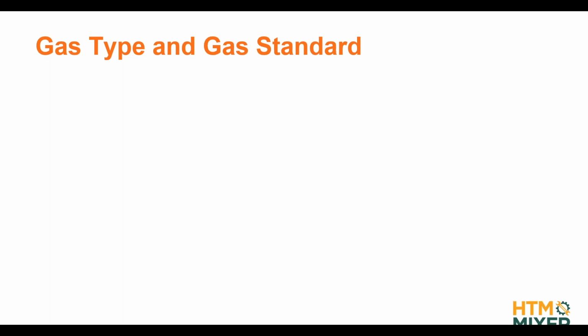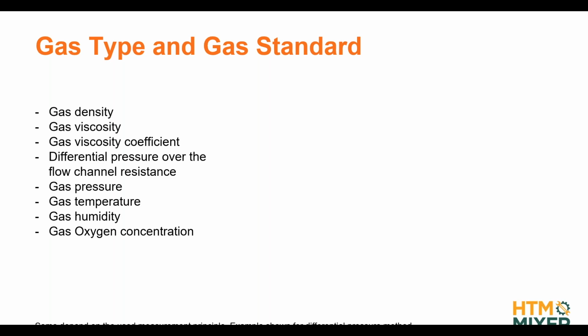All right. So because of that, gas flow analyzers typically need to know a lot of different parameters to be able to calculate the flow rate or a volume. Volume is just flow over time, right? The first three of them on the list here is gas density, viscosity, and a viscosity coefficient. This is typically handled in gas flow analysis by a setting called gas type. So we don't have to tell it exactly this is that density and that's viscosity. There's a preset of different gases that we typically want to measure. For example, air and air-oxygen mixture or CO2, right? And then we can just select from a list the gas type, and then the analyzer knows, oh, okay, this is what we actually want to measure. And this means it knows the characteristics of that gas.